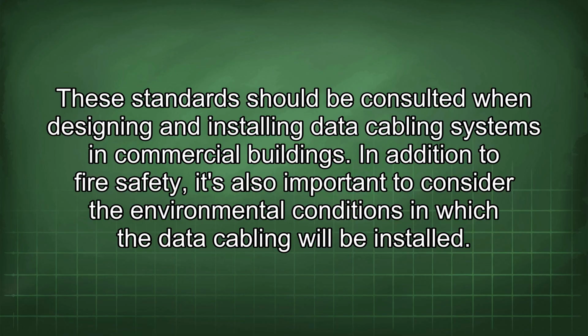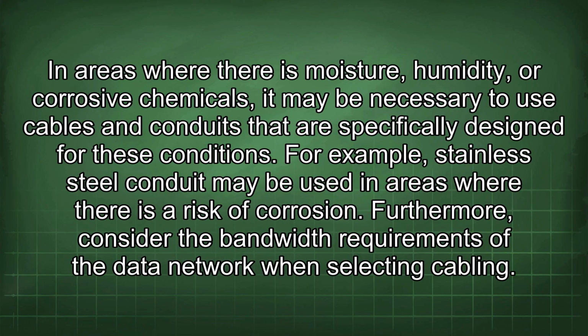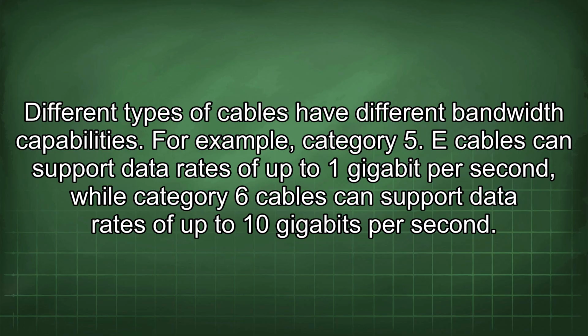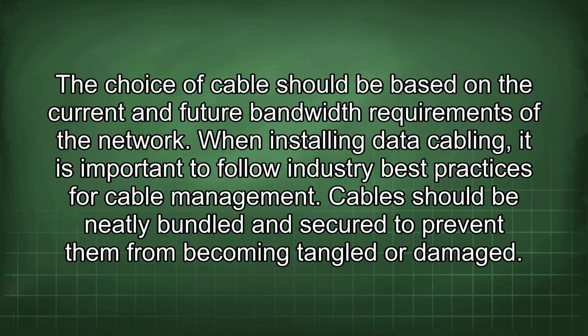In addition to fire safety, it's also important to consider the environmental conditions in which the data cabling will be installed. In areas where there is moisture, humidity, or corrosive chemicals, it may be necessary to use cables and conduits that are specifically designed for these conditions. For example, stainless steel conduit may be used in areas where there is a risk of corrosion. Furthermore, consider the bandwidth requirements of the data network when selecting cabling. Different types of cables have different bandwidth capabilities. For example, Category 5e cables can support data rates of up to 1 gigabit per second, while Category 6 cables can support data rates of up to 10 gigabits per second. Choice of cable should be based on the current and future bandwidth requirements of the network.